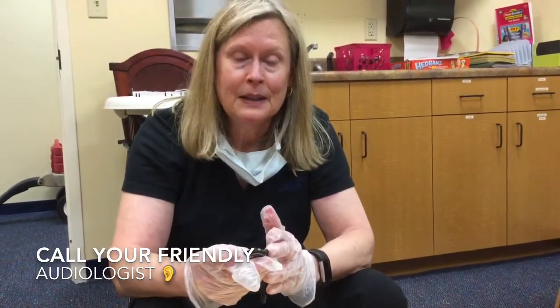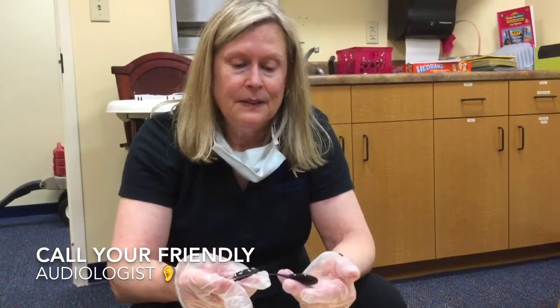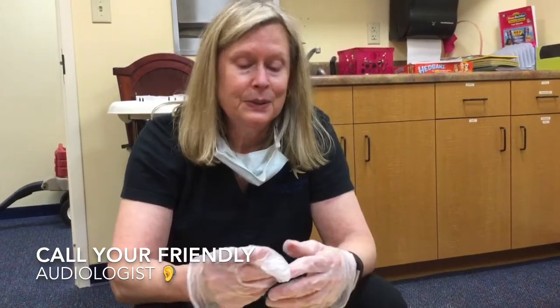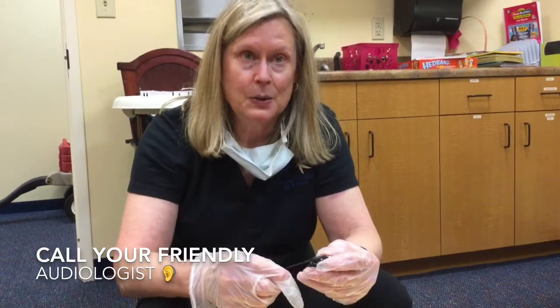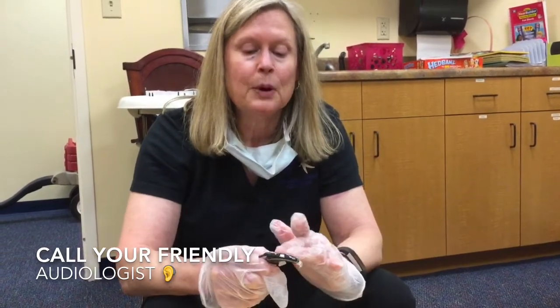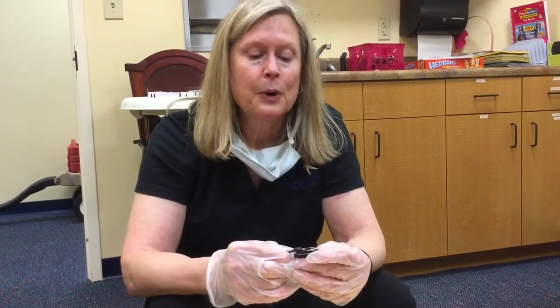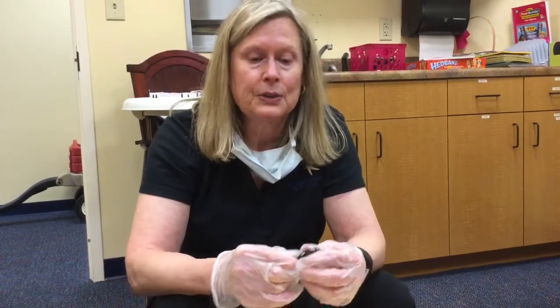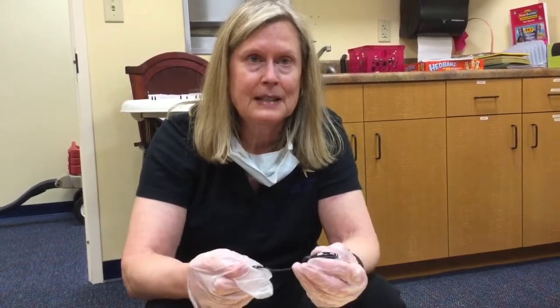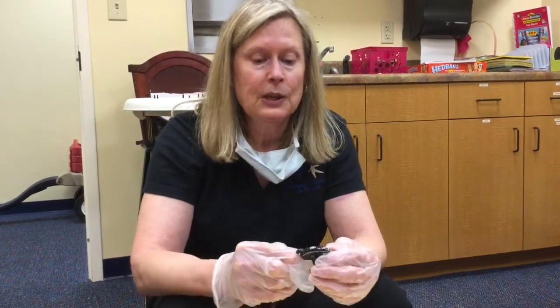If changing your cable coil doesn't help, then what you're going to have to do is let us know. And that means it's a processor issue. If you change out your cable coil and that solves the problem, let us know that too so that we can get you a replacement, or you could call Cochlear yourself if you want and get a replacement. You should always have 1 plus a spare for each ear.